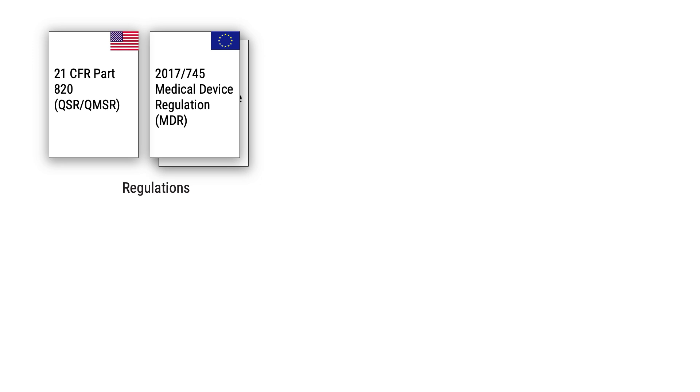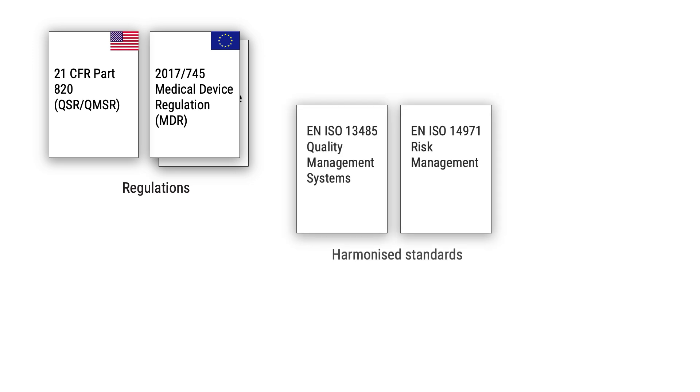In addition to these regulations, there are two standards that are particularly important to be aware of when it comes to process validation: ISO 13485 on quality management systems for medical devices, and ISO 14971 on the application of risk management for medical devices. The vast majority of medical device manufacturers use ISO 13485 and have implemented a quality management system that fulfills its requirements. ISO 13485 in turn refers to ISO 14971 on risk management. Both of these standards are essential in the medical device industry in general, but also useful in a context for process validation.